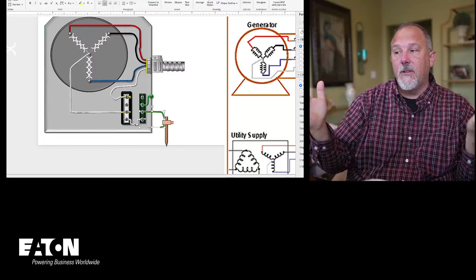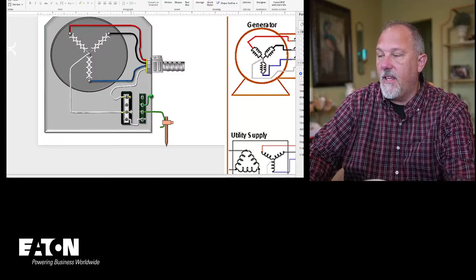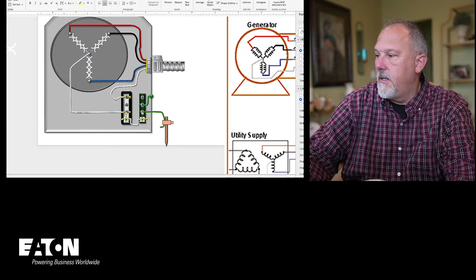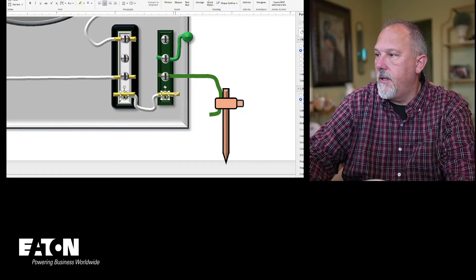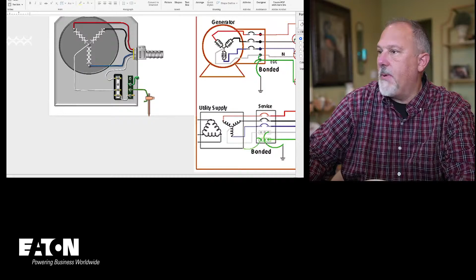And if I don't want a separately derived system, I just delete that and delete the bond, and it's a non-separately derived system. So there will be a jumper inside the generator that gives me that connection. Control Shift. Make sense? Zoom in, get rid of that one, Control Shift F. There we go. So that's basically what's going on in the generator.